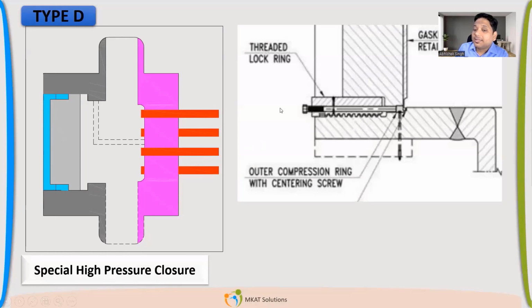So there will be a very high thickness. If you see this point, we have tried to enlarge the left hand side cover. So there is a very high thickness cover, and then there will be a side cover, the channel kind of thing, which will have screws on the outside. Okay. So once you tighten, it will be tightened against this small lip which is projecting. Okay. And then you can have a gasket there, and then again a leak path. So if any leakage is there, you can check.